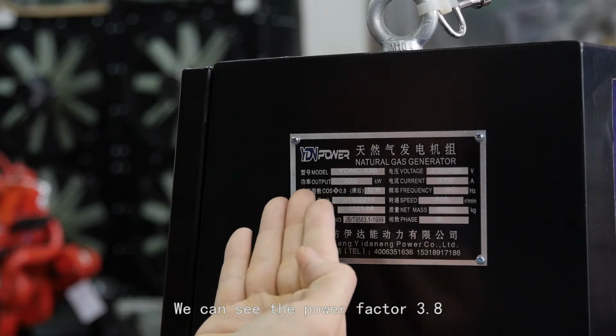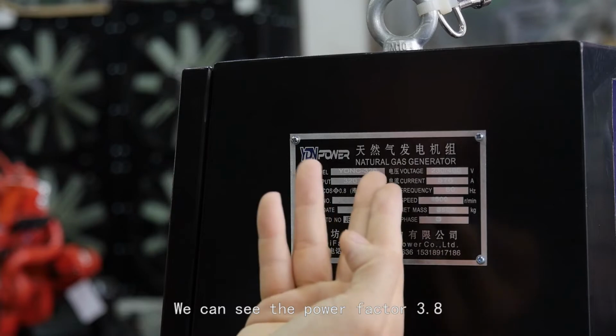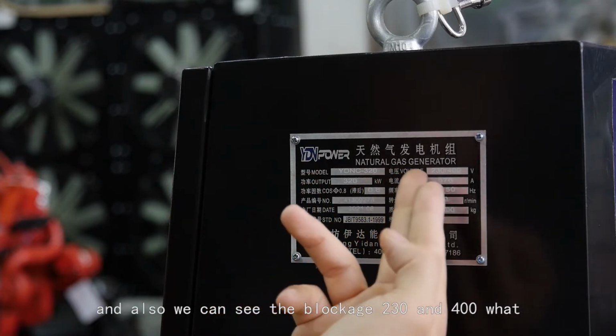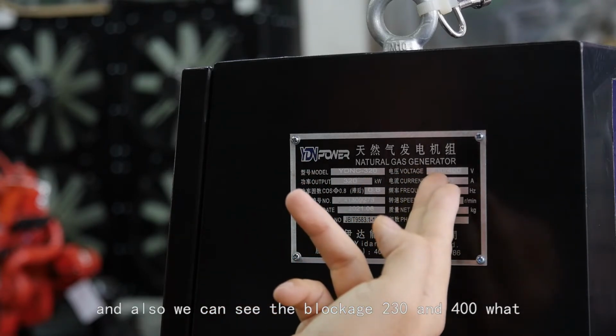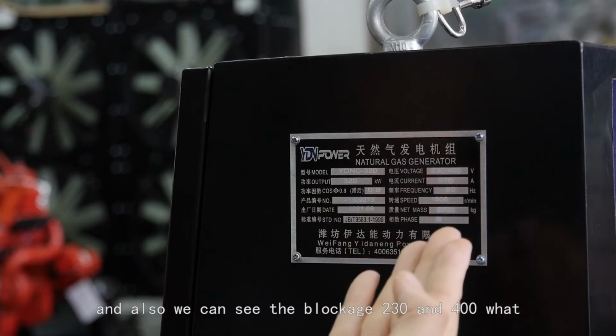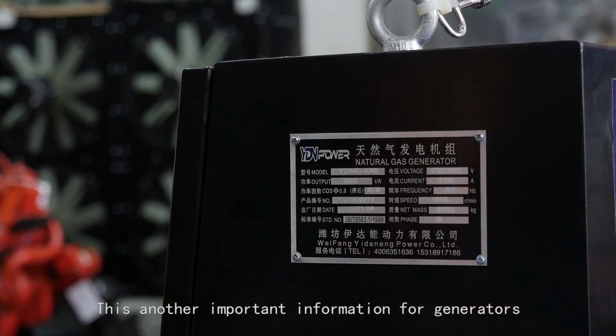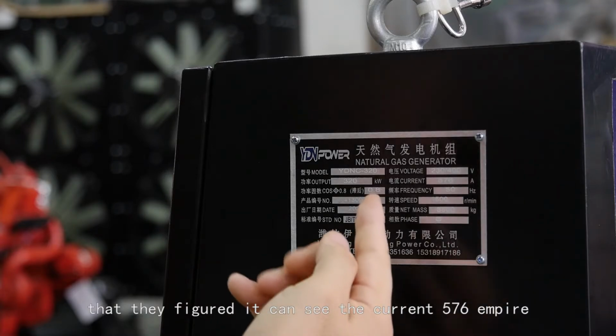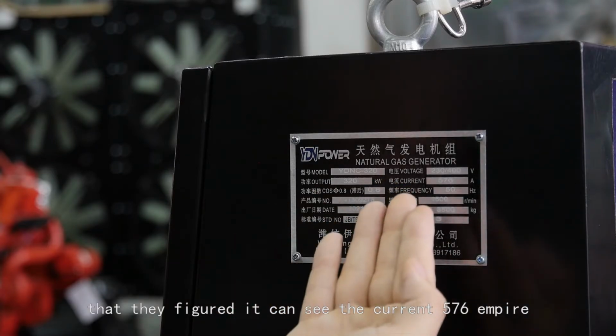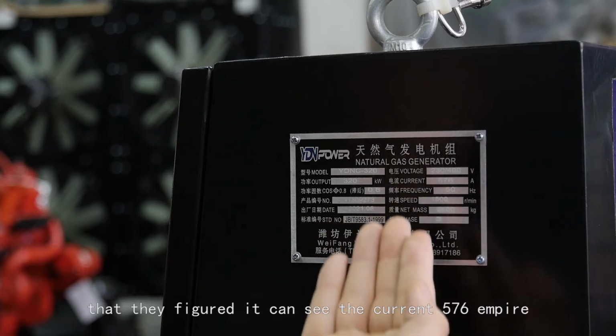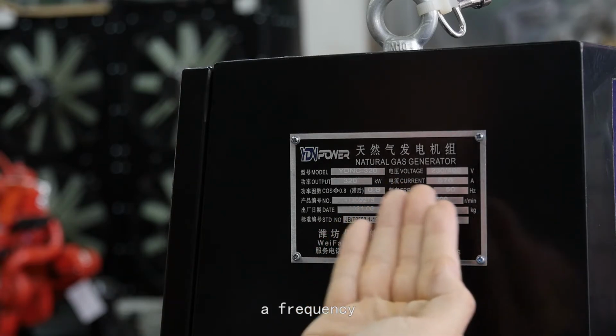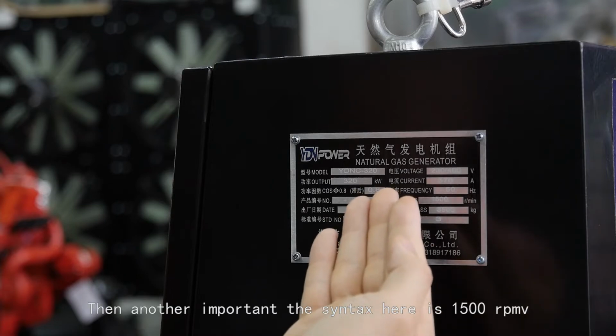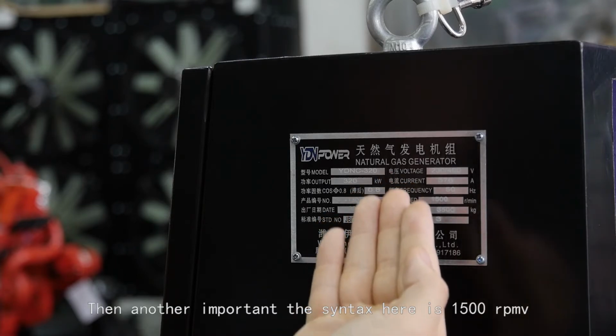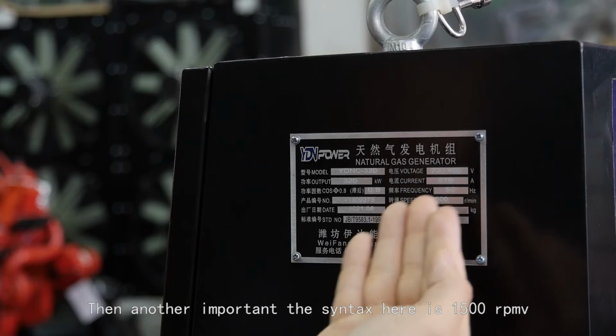Then we can see the power factor, 0.8. And also we can see the voltage, 230 and 400 volt. This is another important piece of information for a generator set. Then we can see the current, 576 ampere, and 50 hertz frequency. Then another important index here is 1,500 RPM.